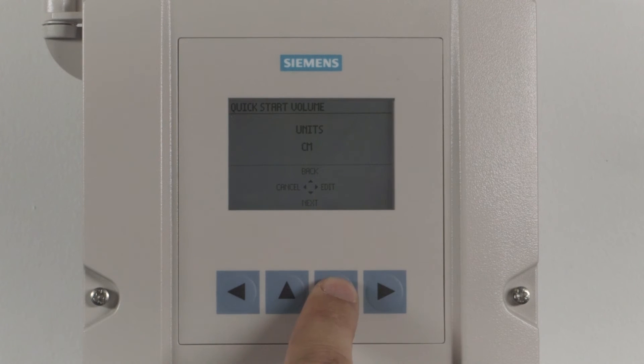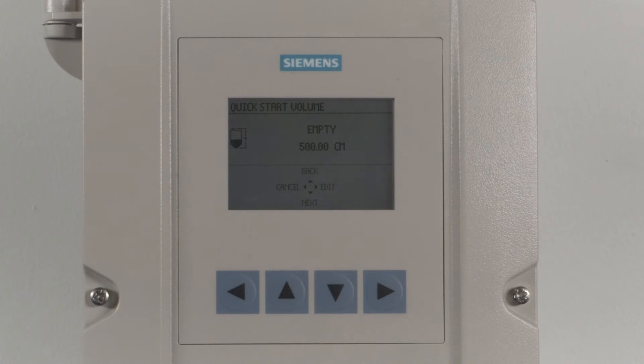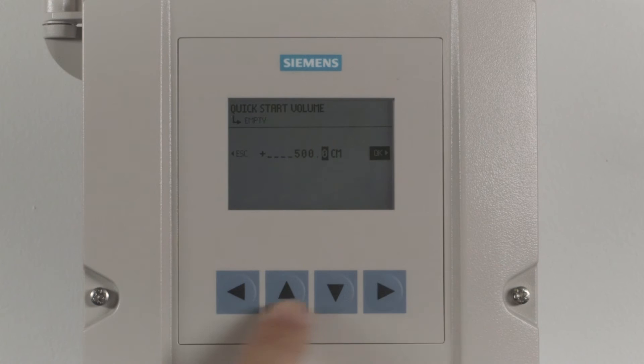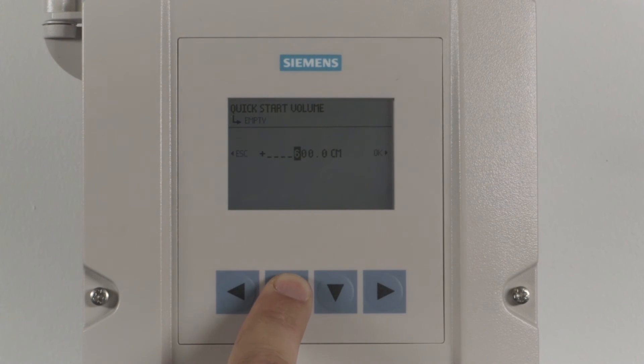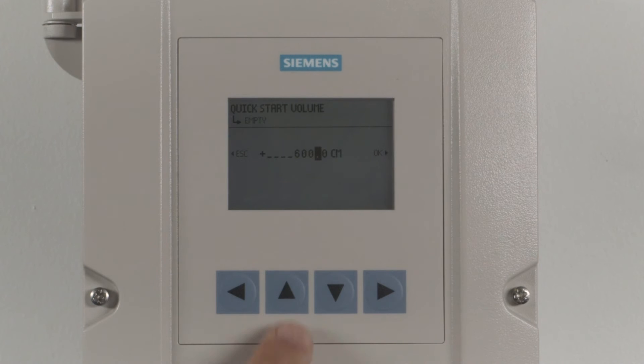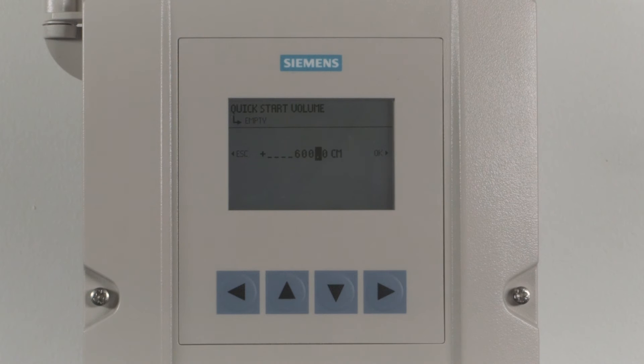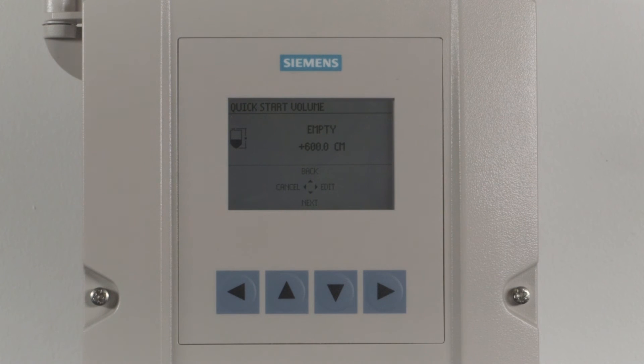Press the down arrow to select Next to proceed. The next step in the wizard is to enter the empty distance — the distance from the face of the transducer to the process empty point. Press the right arrow to modify the empty distance value. Use the left and right arrows to move the cursor and the up and down arrows to modify the value. To move the decimal point, position the cursor over it and use the up arrow to move it left or the down arrow to move it right. Once entered, press the right arrow to highlight OK, then press right again to accept the empty distance. Press the down arrow to proceed.